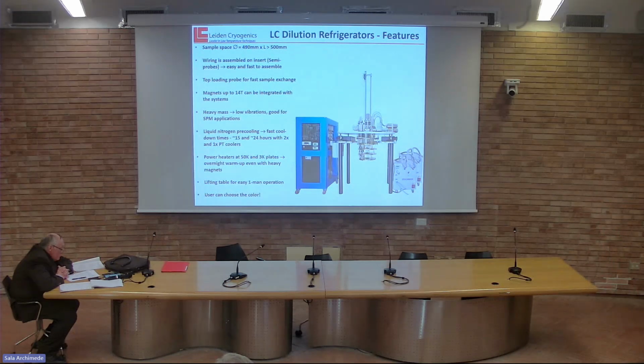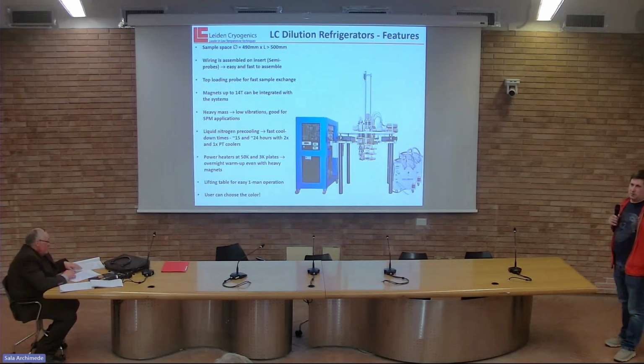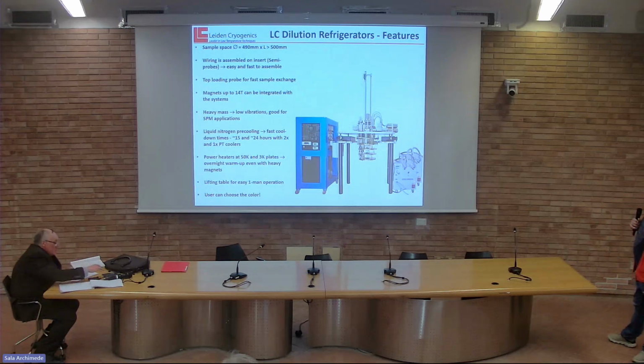They're heavy, but it doesn't mean that they take a long time to cool down. So we use a liquid nitrogen pre-cooling circuit where you can circulate liquid nitrogen through the dilution refrigerator. And in principle, with systems with 2 pulse tubes, you can cool to 4 Kelvin in about 15 hours. And the systems with 1 pulse tube, it takes around 24 hours.